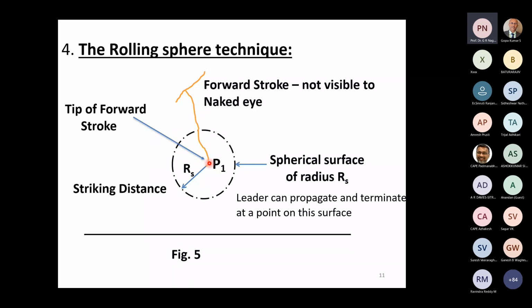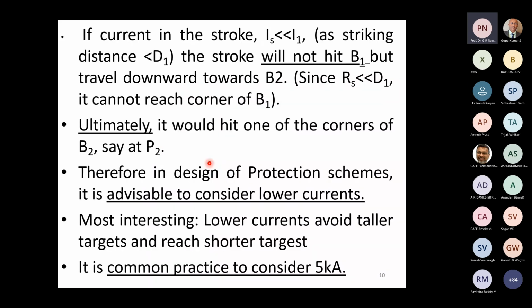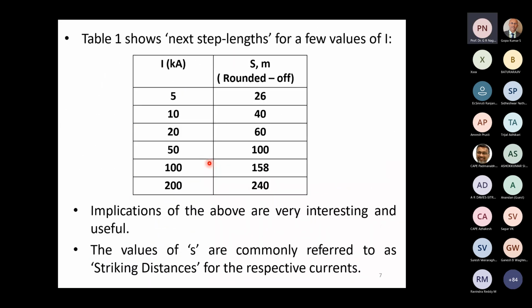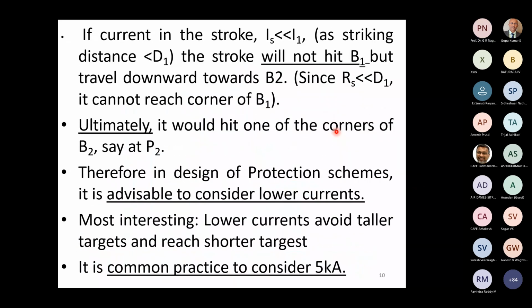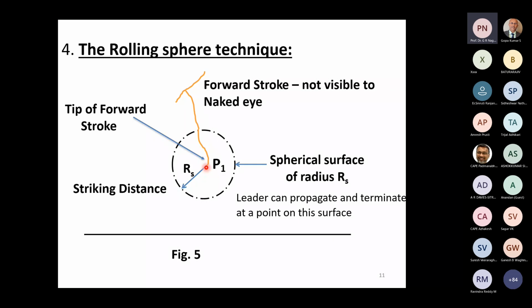For 5 kiloamperes, what is the striking distance? We have seen in the previous table. For 5 kiloamperes, using that particular equation, the next step distance is 26 meters. Or people have used 25 meters as a rounded-off figure. If you want to play even safer, use 20 meters. So let us say that we use a sphere of radius 25 meters as the spherical surface onto which the stroke of 5 kiloamperes can go and hit. So if I use a sphere of radius 25 meters, the 5 kiloampere stroke will come onto any point on this spherical surface.